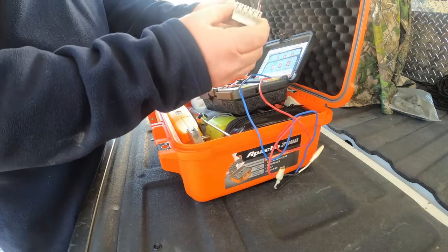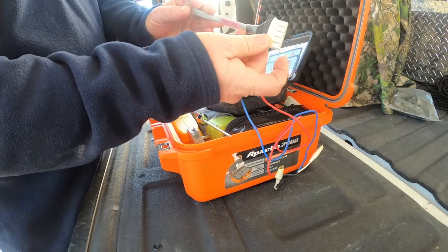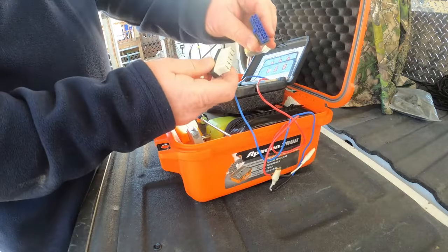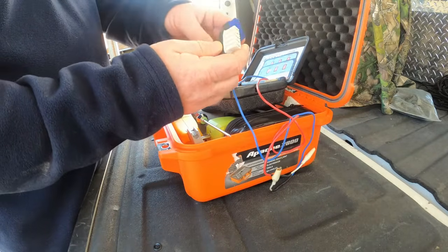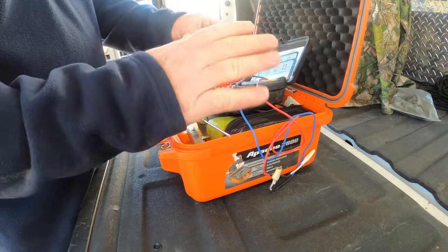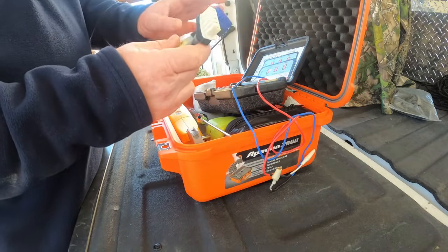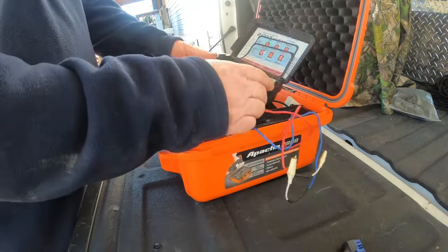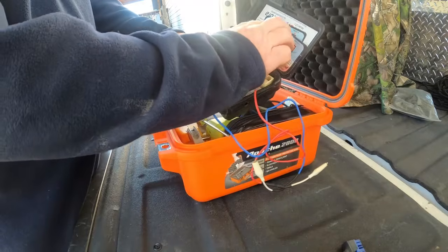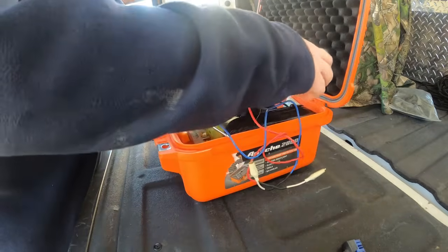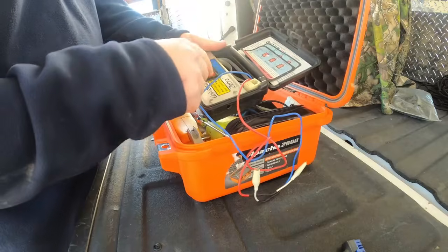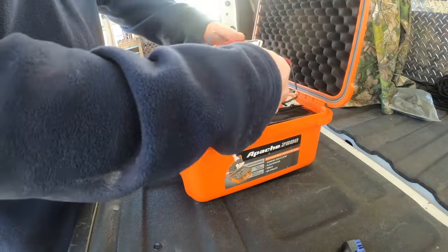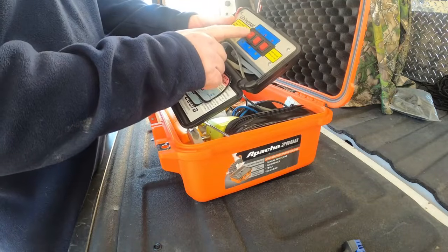You can get a connector that will go to an X13 type motor. You can get a connector that goes to a 16-pin type motor, and then you can get a connector that'll go to your serial port motor, but I don't trust that because that's communicating. There's specific ways you need to troubleshoot that. But once you get everything tied in and connected, each one of these adapters tells you how to operate this thing. But you can go in here and you can actually energize your different speeds for your motors.